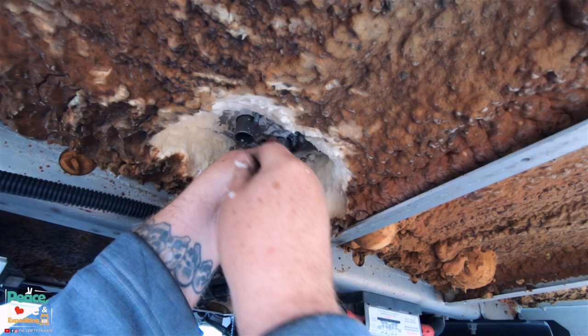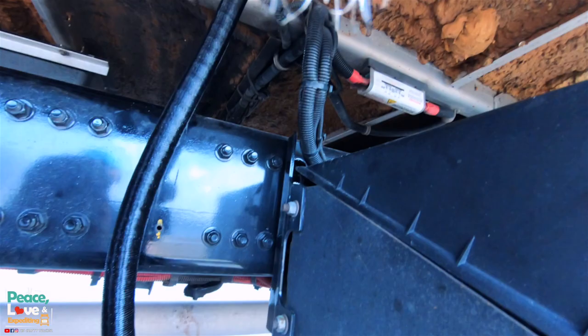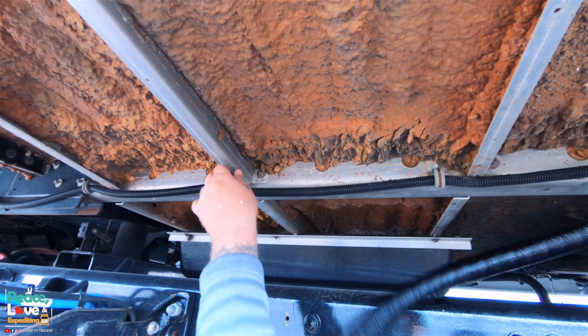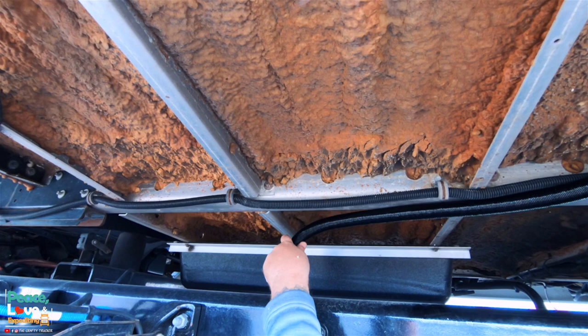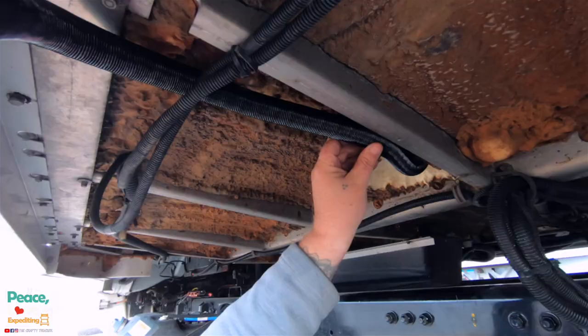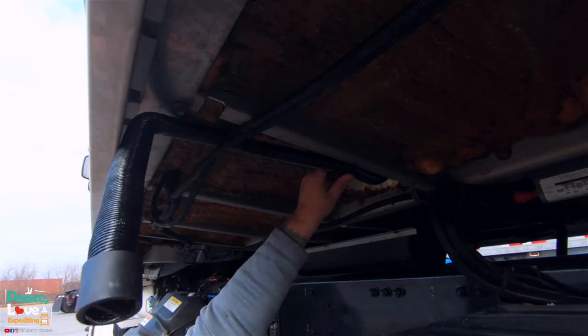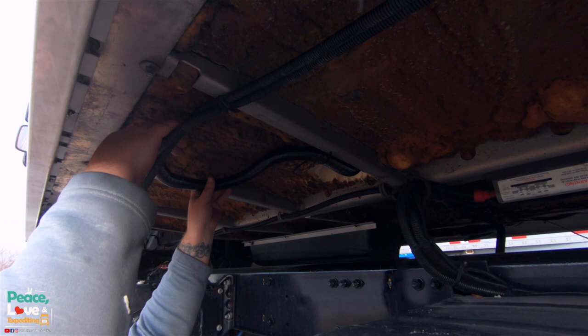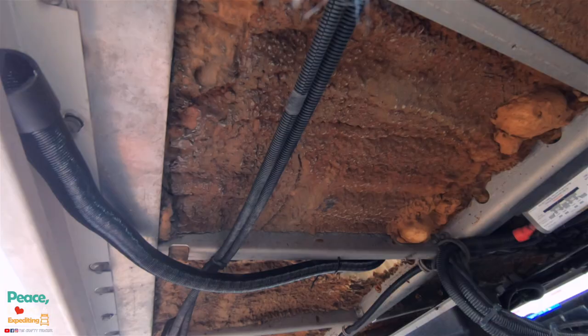All right. Give that a little snug tug there, make sure it's nice and tight. Now we're gonna wanna mount this where it's pointing downward. We don't want any high points because we don't want water getting up in this hole and then collecting like right there. All right, so we're gonna get this mounted along this rail here. We're not gonna go too tight because we don't want to put any bends in this. Next, I'm gonna add another zip tie to come along with these.